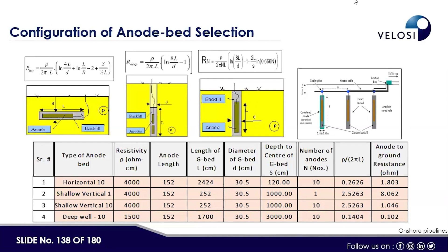This also varies from one area to another. In one location we may have a CP station, and in some locations one CP station with one ground bed system can protect 30 kilometers on either side, meaning it can cover up to 50 to 60 kilometers. But you have to be careful and do the attenuation calculation.